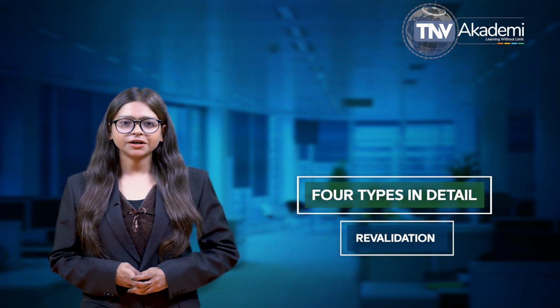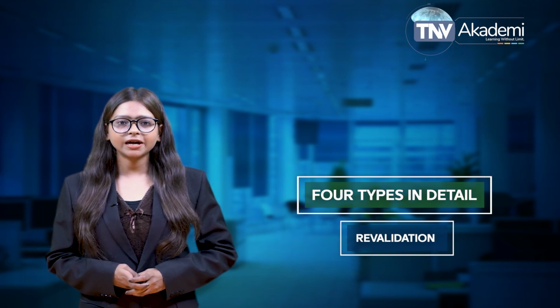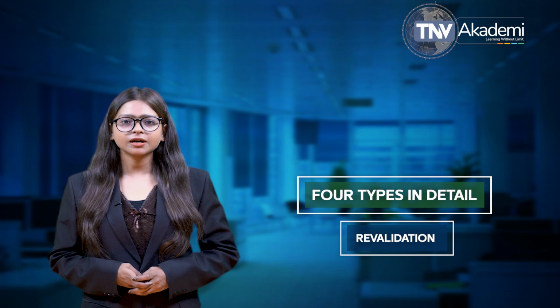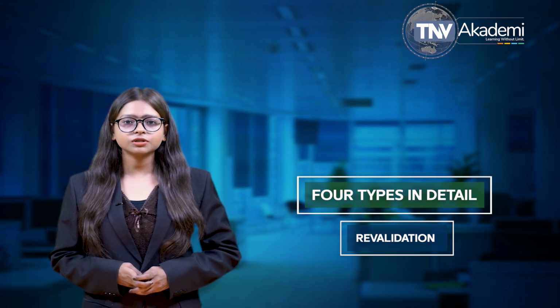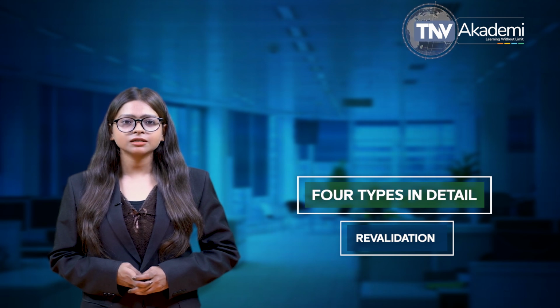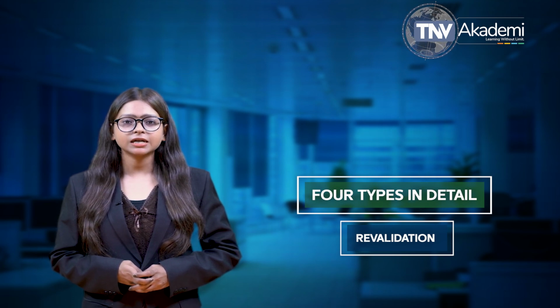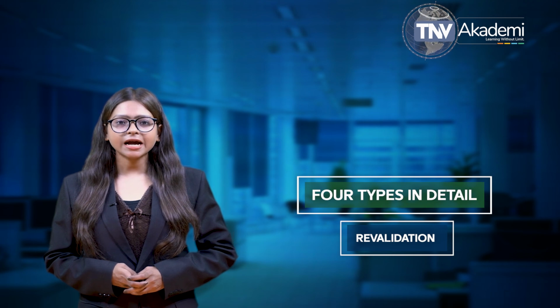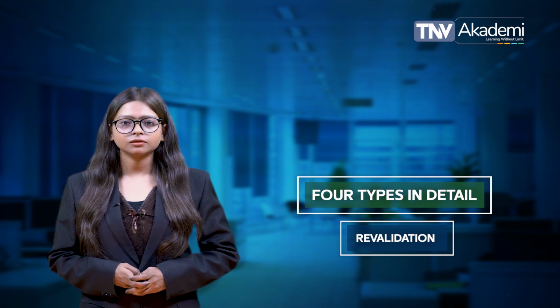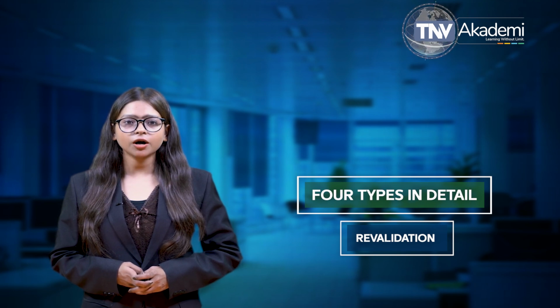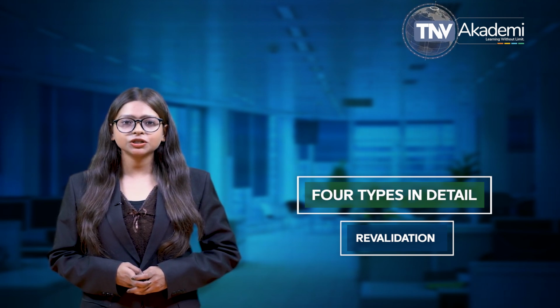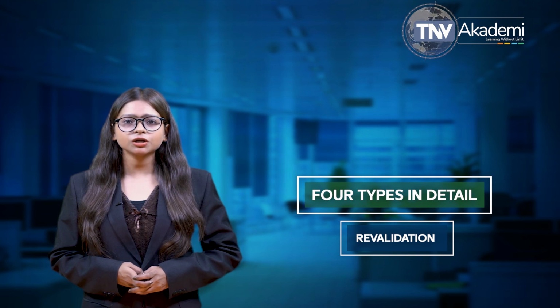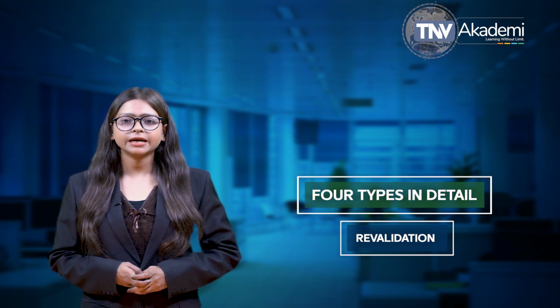Type 4. Revalidation. Revalidation is more widely used for medical devices than drug products. It is executed when prospective validation reaches a conclusion that the manufacturing process is unable to produce the product consistently. Moreover, criteria for revalidation may be indicated in the original validation protocol. The revalidation process may not be as comprehensive as the initial validation, especially if the situation only calls for some aspects to be repeated. We have now come to the conclusion of this session.